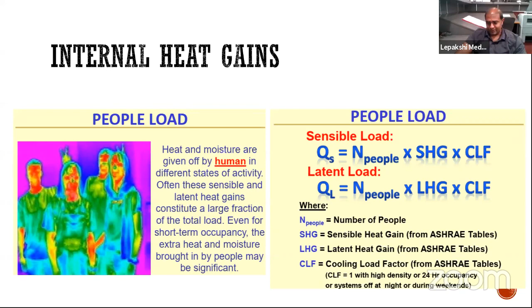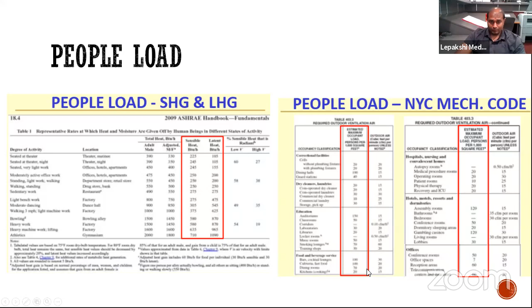This is from the ASHRAE handbook. There are 4 different books from ASHRAE where you can get all this information in tables. For example, if you're sitting in an office, a theater, a factory, a dance hall, or doing something like bowling in a bowling alley, these are the amounts of sensible and latent heat gains you release to the system. We pick these numbers and multiply by the number of people in that space. That's how you calculate how much load is given to the system by the people, and that's how you determine the people load.